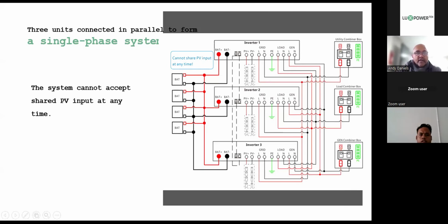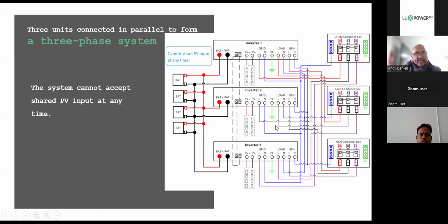Okay, and then the next one, we're going to have a look at the three-phase system. Exactly the same. PV cannot be shared. Here we've got a shared battery bank in a three-phase parallel. Okay, shared battery bank, we spoke about it. If one phase is idling, the other two have access to the full battery bank. No PV sharing, and then obviously your output is shared. Remember, in three-phase, the neutral is common. Okay, neutral is common among all of the phases because we're putting out a star configuration.